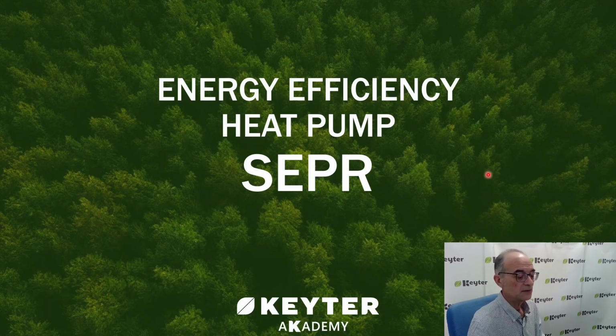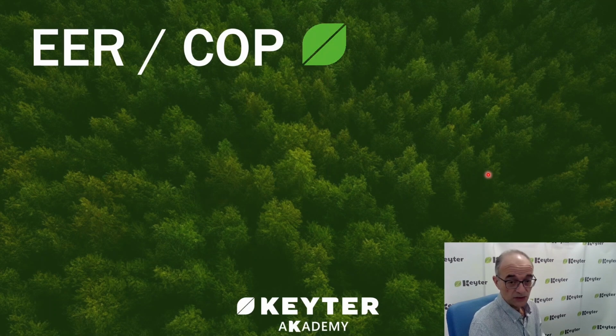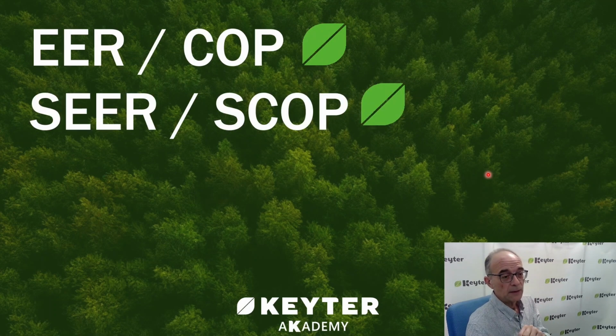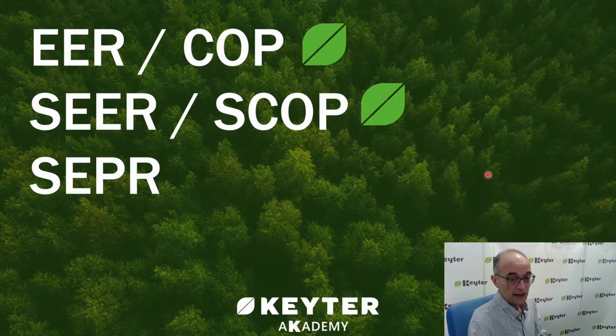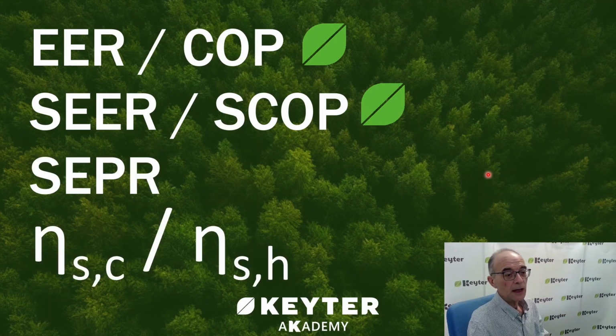operation of process chillers. We already saw in the first video the concept of EER and COP, that snapshot in time. Later, we looked at the concept of seasonal COP, which would be like a video, the average EER and COP over the whole year. In this case, we're going to look at process chillers, and then we'll discuss the ETAs, the seasonal efficiencies. As we've mentioned so far, these concepts refer to final energy, whereas ETA refers to primary energy. It's a concept that we'll see ultimately shows that heat pumps truly have a very strong renewable character.